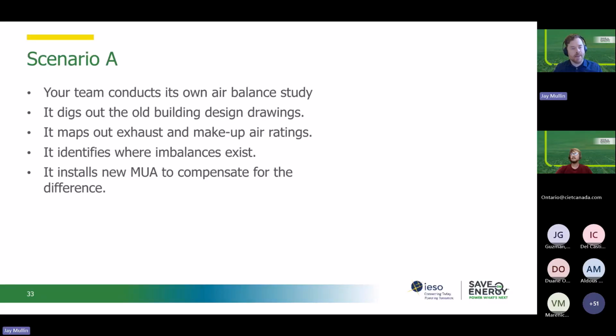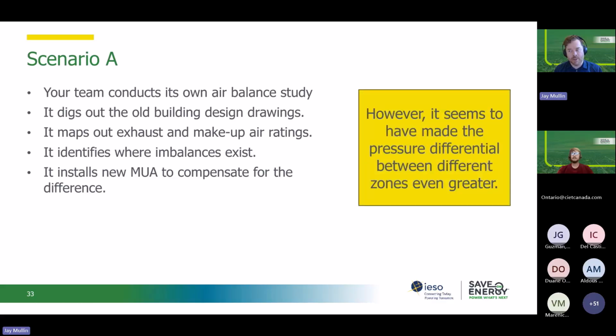So in our first scenario, an energy manager notices some symptoms of negative facility pressure across the facility. The team conducts their own air balance audit. They dig out the old building design drawings, and use those and equipment specs to map out the exhaust and makeup air ratings across different zones. They've identified where the imbalance exists, and they see where the mass balance indicates the need for a new makeup air unit, and they install a new makeup air unit. Unfortunately, it seems it's made the pressure differential between those zones even greater. So it didn't solve the problem, it actually made the problem worse.